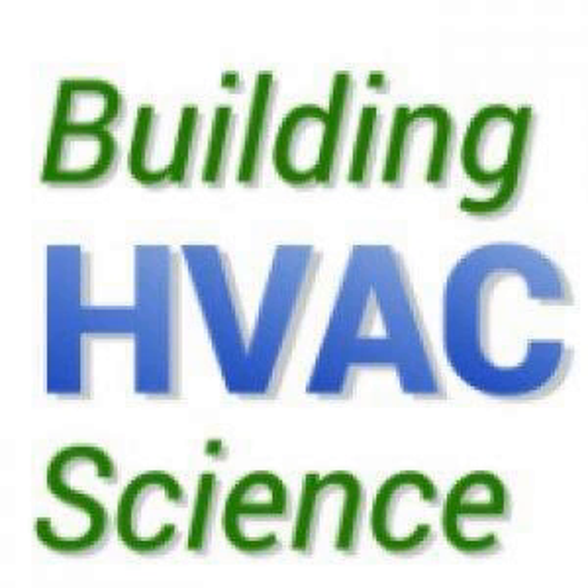I can tell you, I'm not scared to talk about the ones I got in trouble on. One thing I got in trouble on was not doing the math on transfer fans. I don't know if you've heard the myth of transfer fans—that in a passive home you could use one BTU head, one ductless head at the end of a building, and then use transfer fans in the walls to move air between closed-door rooms. So instead of having registers in a bedroom, you'd have a transfer fan between maybe the hallway and the bedroom.